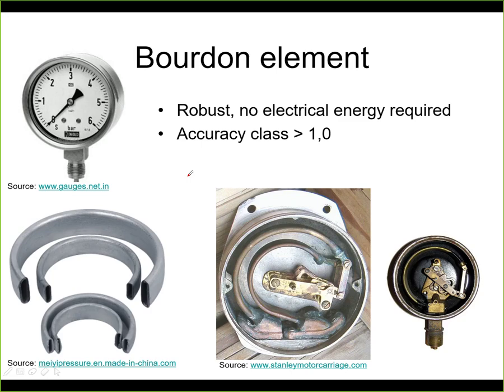Of course, it could be equipped with an electrical output. You could sense the angle of the needle, you could have any kind of position sensor mounted on there, but it's not very typical to find Bourdon elements with an electrical output. The Bourdon gauges are very robust, so they can work in environments where you have vibrations, where you have changes of temperature. So they are very common in many industrial applications, but as I said, they are not connected to any control system. The accuracy class is typically above 1%, so it's not the most accurate pressure gauge, but if you just want to read the pressure somewhere in your application, this is quite sufficient.